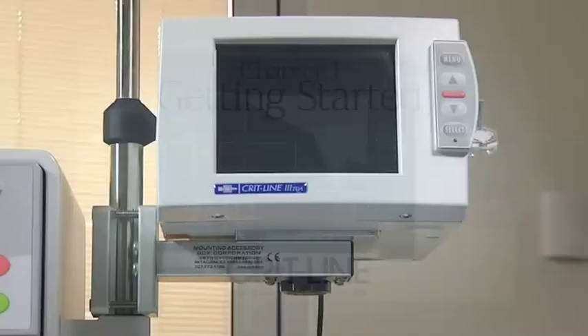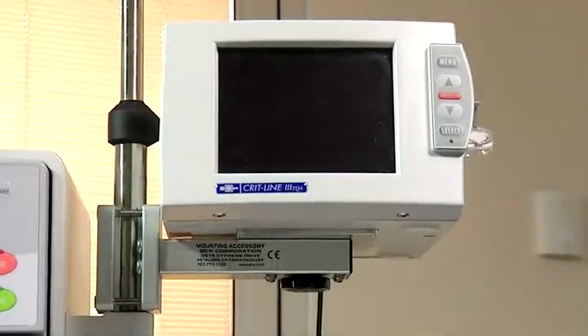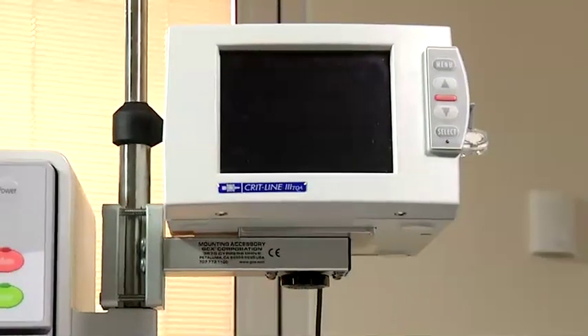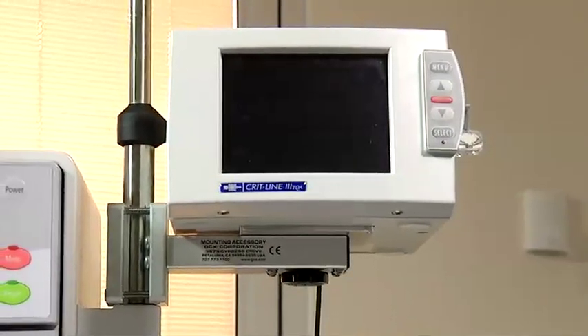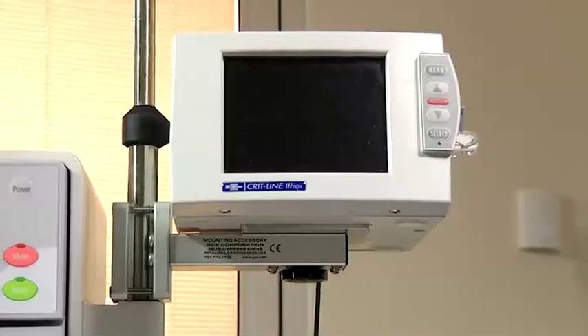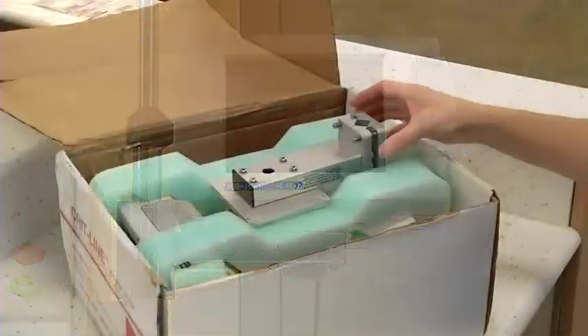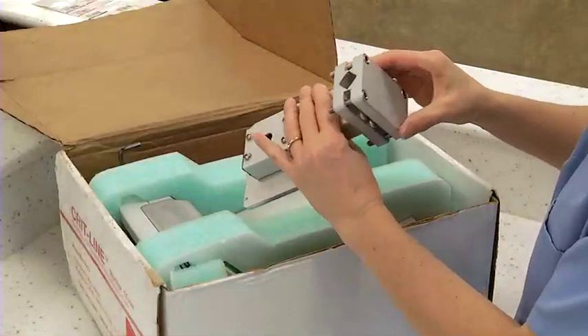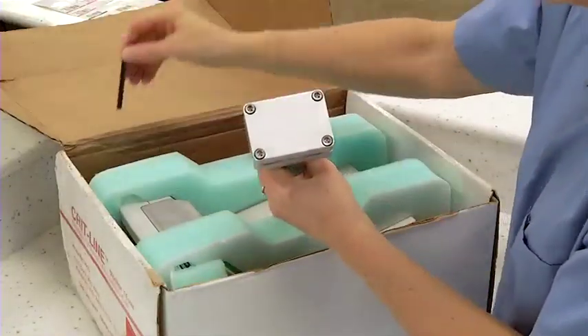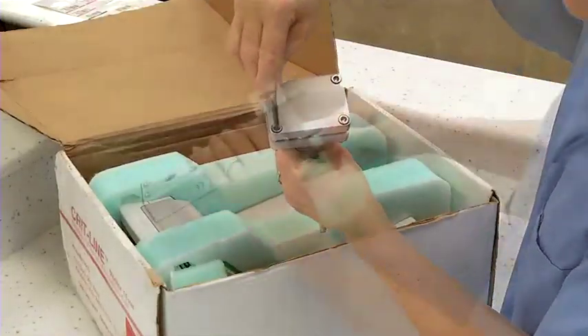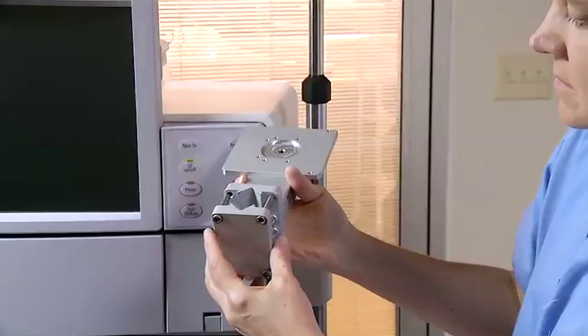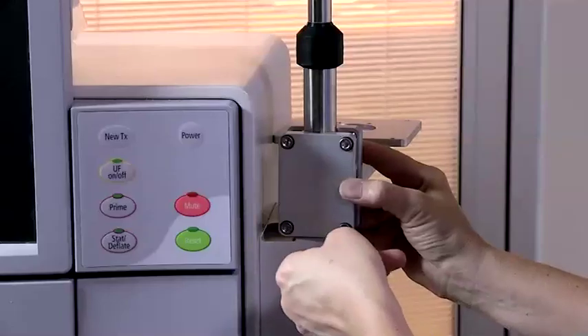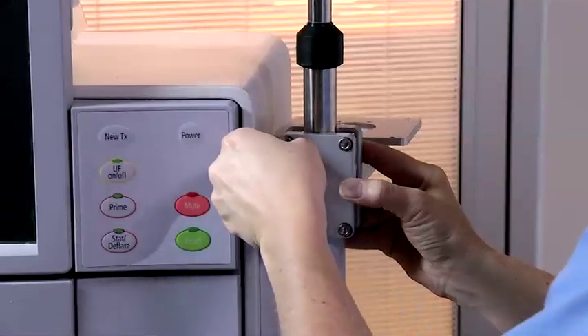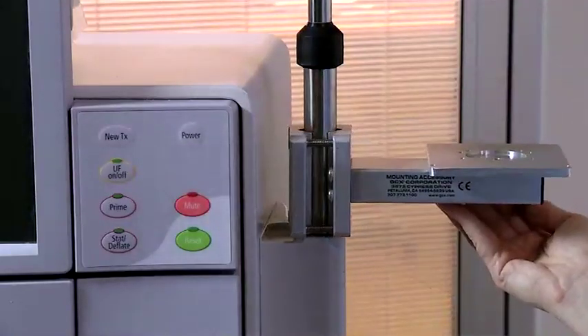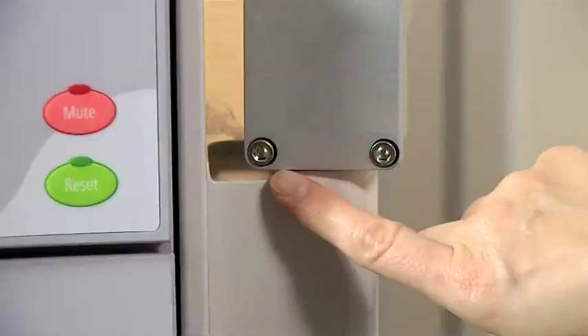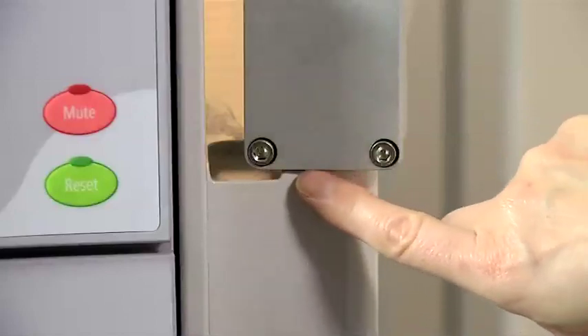The CritLine monitor is designed to mount on the IV pole on the 2008 hemodialysis machines. To attach the CritLine monitor to the 2008 series IV pole, remove 4 screws from the pole mount bracket using the hex wrench included in the CritLine monitor box. Secure pole mount bracket to the wider top portion of the IV pole by replacing the 4 screws with the hex wrench. The pole mount should rest comfortably on top of the IV pole holder attached to the machine.